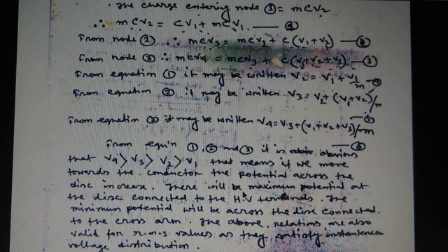There will be the maximum potential at the disk connected to the high voltage terminal. The minimum potential will be across the disk connected to the crossarm, because we already know that the crossarm is directly connected with the ground point. The above relations are also valid for the RMS value, as they satisfy instantaneous voltage distribution.